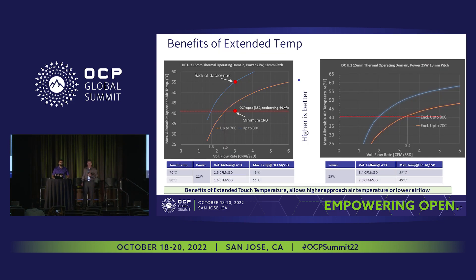The benefits of extended temp are simple — higher is better. This shows the approach ambient temperature versus the volumetric flow rate in the platform. If we can improve the ambient temperature, we need less airflow — either increasing the ambient temperature or requiring less airflow. The orange shows the 70 degrees C traditional touch temp, and up to 80 degrees C is in blue. With the 22 watt U.2 drive, we are barely meeting the OCP spec of 35 degrees C, at around 3 CFM per SSD in the platform for this form factor. When we enable this feature, we are able to improve that quite a bit.